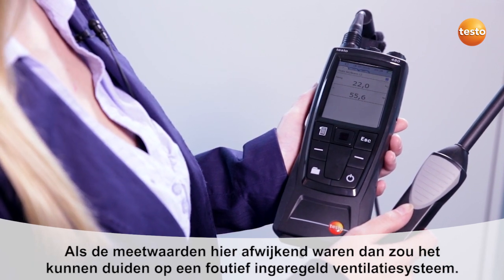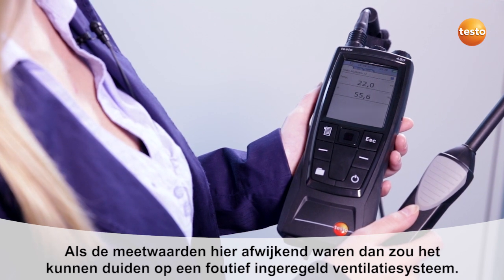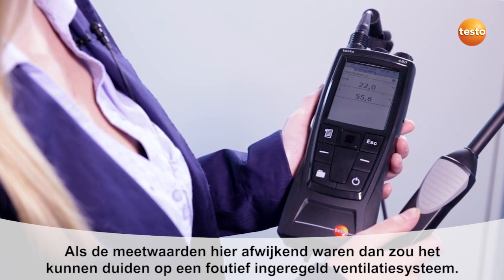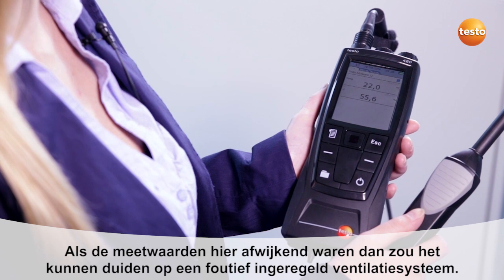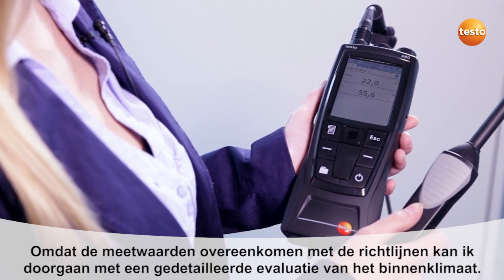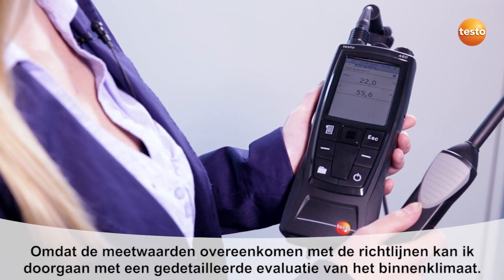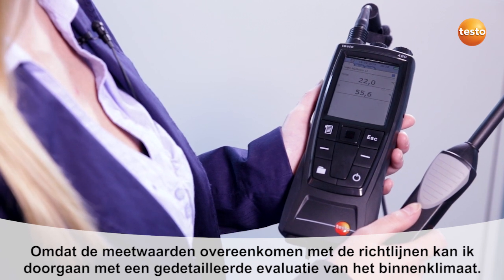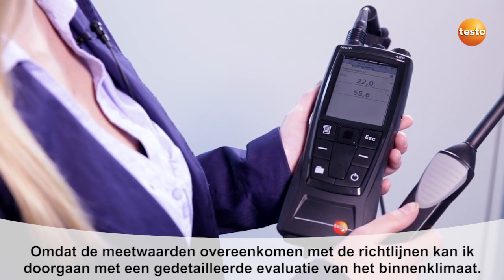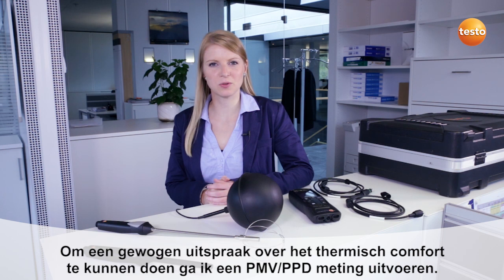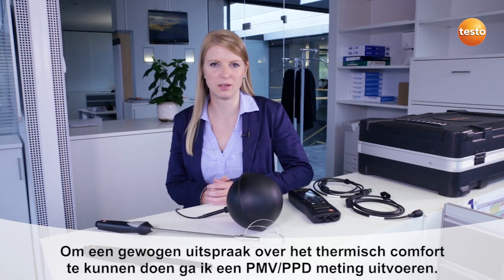If the measured values here already showed a considerable deviation from the comfort range, this would be due to an incorrectly adjusted ventilation system. Since the values correspond to the respective comfort ranges, I can continue with a detailed evaluation of the room climate. In order to be able to judge whether the ambient conditions are actually causing the thermal discomfort, I'll now conduct a PMV/PPD measurement.